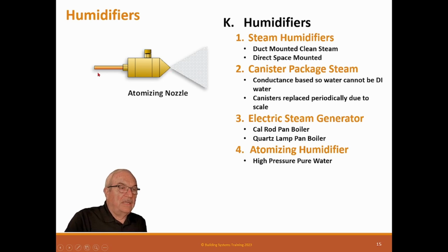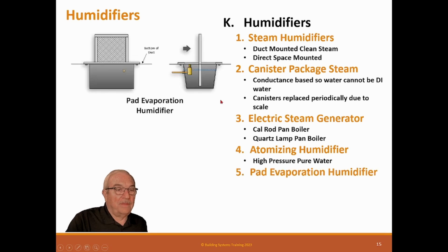If you have high calcium, magnesium water, you need to clean the water. Now, this pure water RO would work perfect for these. Otherwise, these are going to put out that mist, and anything these spray on, if they have calcium and magnesium, turns out to be white. It will paint it with that stuff. You realize what's going on in your lungs.